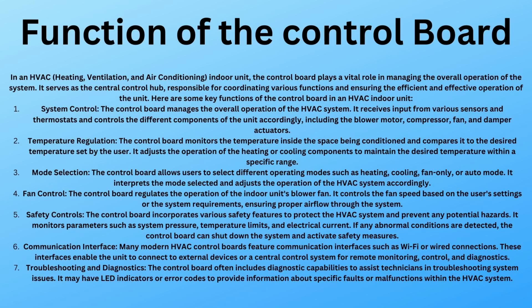Fan control. The control board regulates the operation of the indoor fan unit's blower fan. It controls the fan speed based on the user's settings or the system requirements, ensuring proper airflow through the system. And let me go over some. Nowadays, some have what they call fan modules. It keeps the fan blower motor from ramping up so fast. It'll have a control module on the back. Allows that fan to slowly come up to operating speed. That allows it to balance pressures as it's first kicking on.